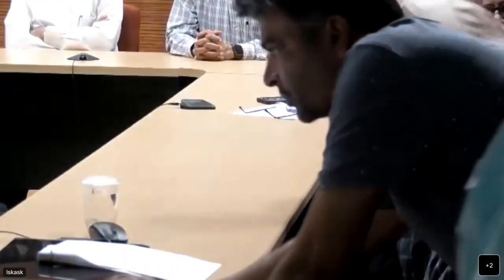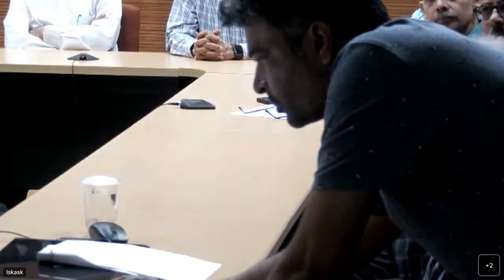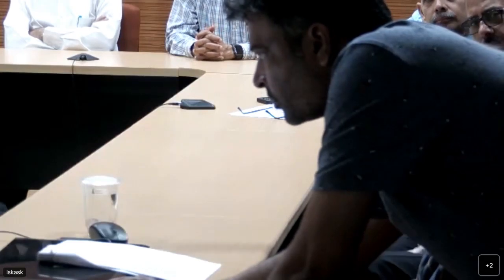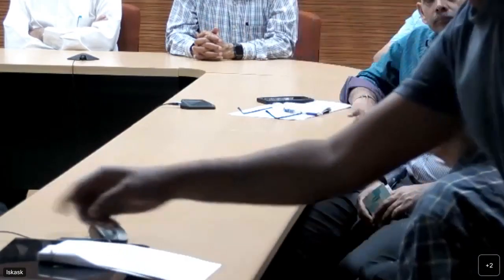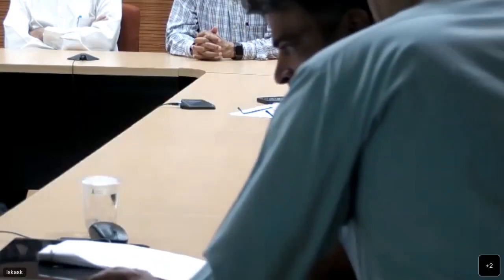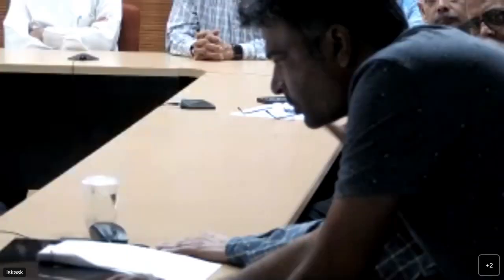So how to put the sealing plug, compress it against the sealing face, and then lock it in place, because the fueling machine has to go away after installing it. See, what fuel handling engineers, particularly at site, dread is that the fueling machine is clamped onto the channel and it doesn't come out, or you're not able to proceed with the operation, which you call a hang up. This hang up of the fueling machine is the dreadliest thing. When you reach that, you're obliged to shut down the reactor. Very often you may have to cool, then access the vault and do a repair. Nobody likes to do this.